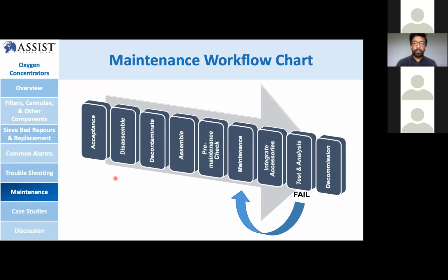Usually whenever we accept, we consider every medical equipment contaminated, but because most of the equipment that arrives here is already very visually dirty, we've made a decontamination guideline which we submitted to the Ministry of Health, and every hospital biomedical engineer is expected to clean it. That's why in the acceptance test we visually check it and accept.